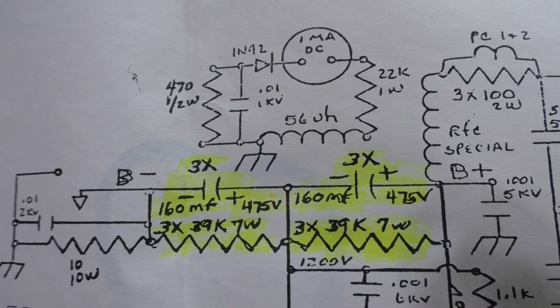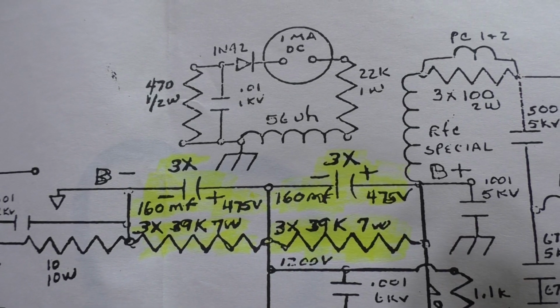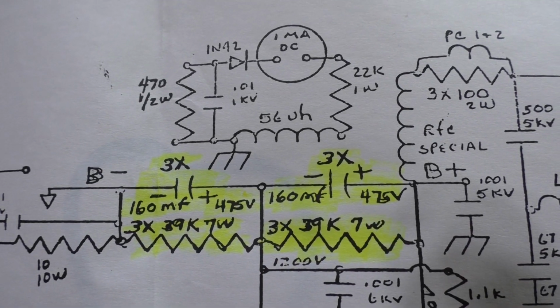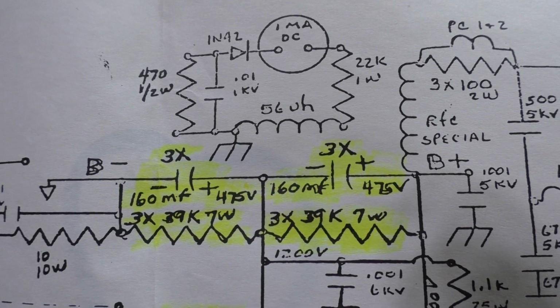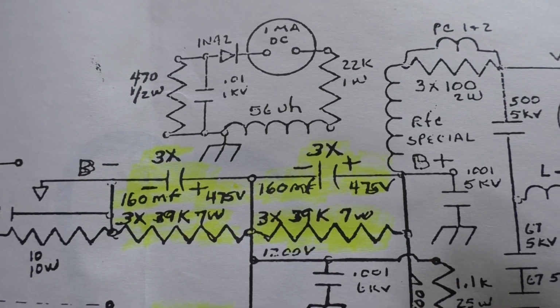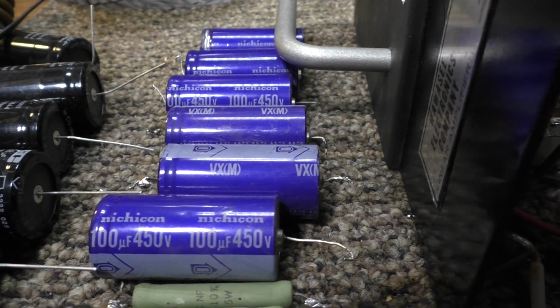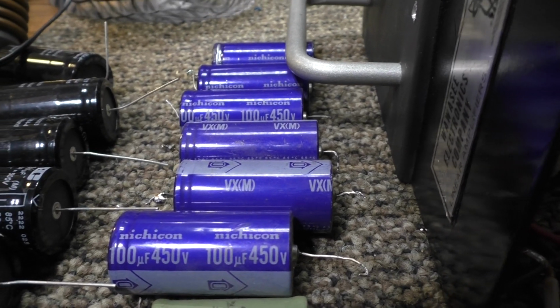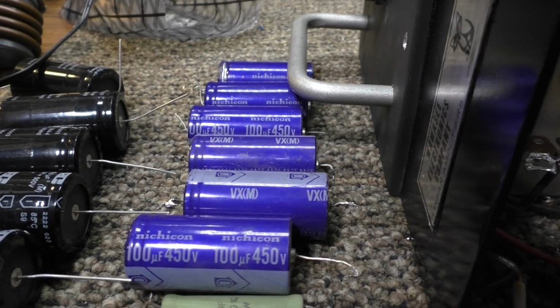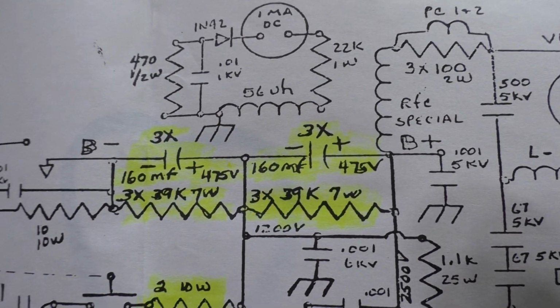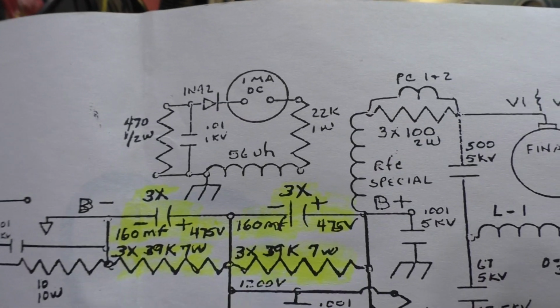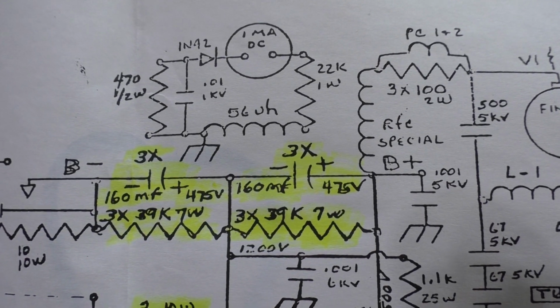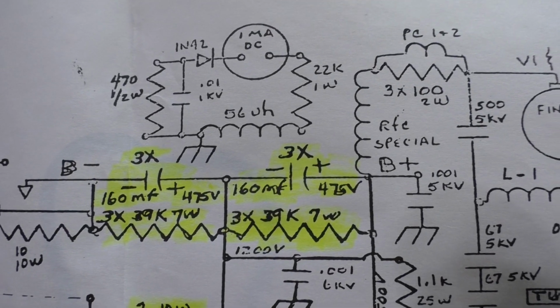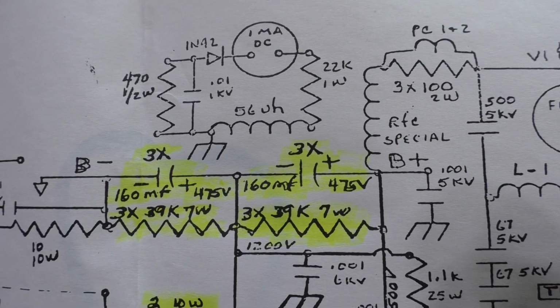I dug out a schematic here and highlighted it in yellow. The original had 160 microfarad at 475 volt for the capacitors, and somebody had gone from 160 to 100 microfarad, and was wondering why the high voltage and current wasn't holding up as it should. Both of those are underpowered from the original: on the microfarads you went from 160 to 100, and on the voltage you went from 475 to 450. So that's not good on either one.